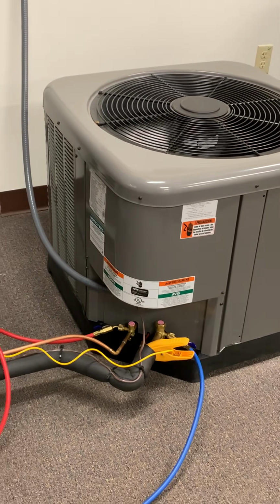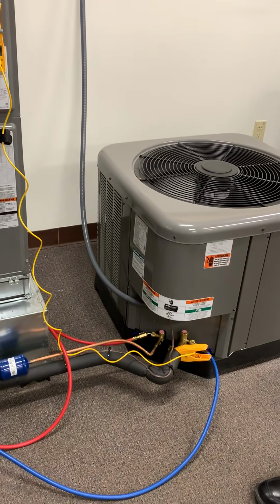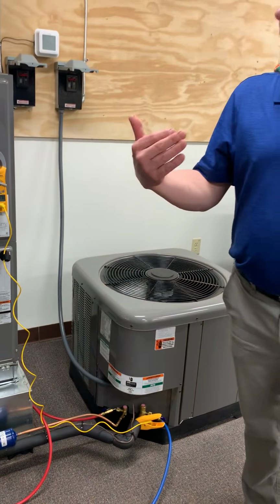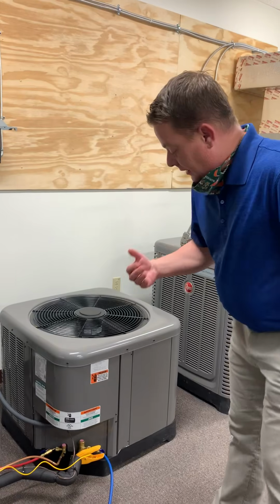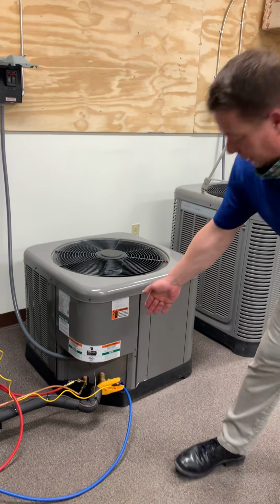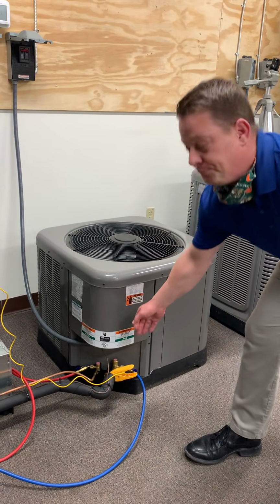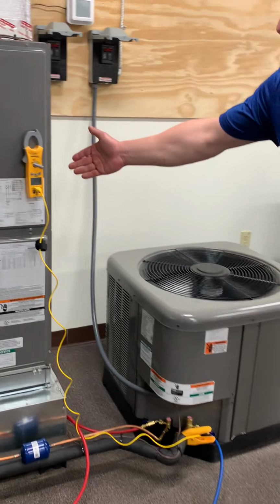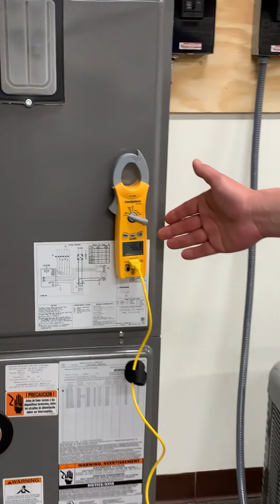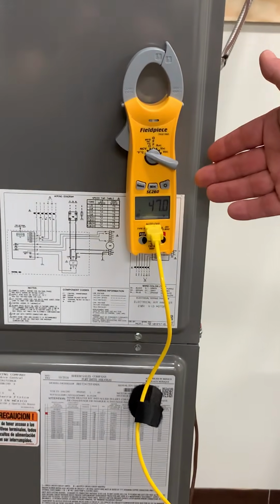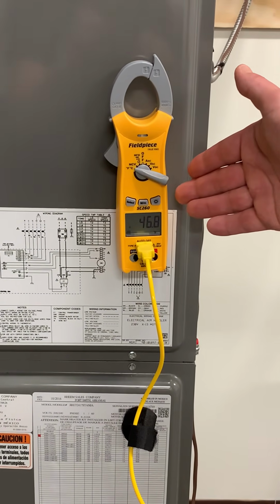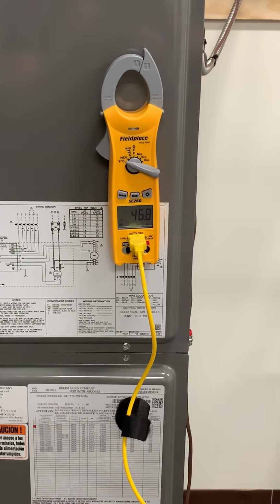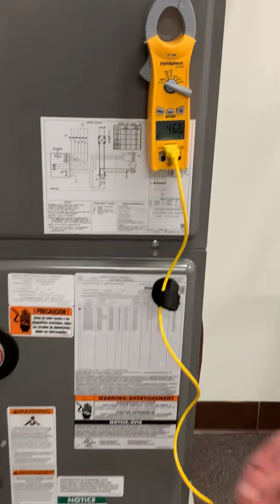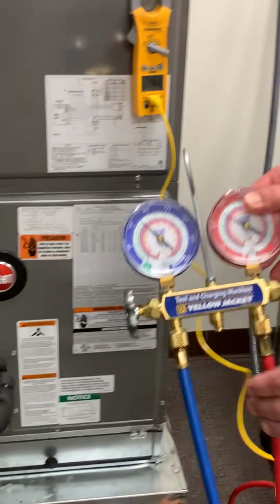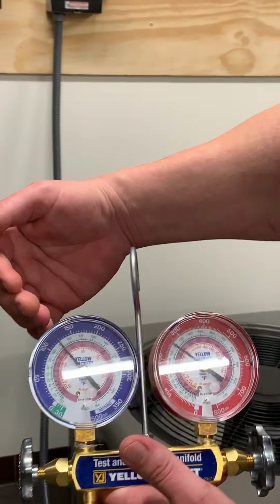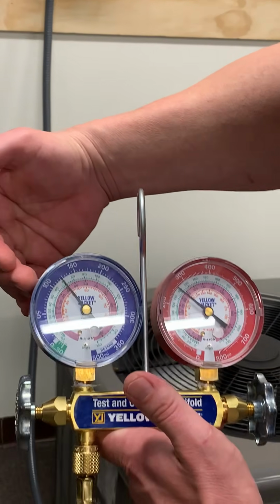So the first thing we're going to look at is what is our suction line temp. We're going to measure superheat first, so we need to know what our suction line temperature is. And we want to measure it fairly close to our service valve. You can see, looking at my Fieldpiece meter, I've got about 47 degrees on my suction line. So I need to notate that number, and now I need to go to my refrigerant gauges, and I want to look at my suction pressure.